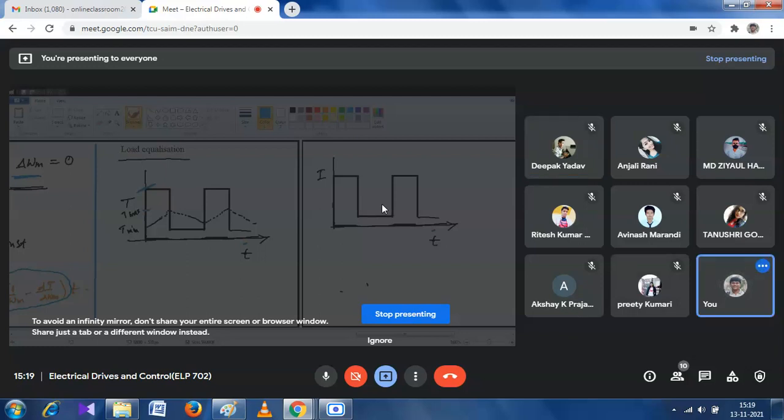एक्चुअल जो सिस्टम है वो फ्लक्चुएटिंग नेचर है. The nature of the current of actual system is fluctuating, so it may disturb the voltage level of that system. To reduce the fluctuation in voltage level or say stability of that system, we have used such a thing that we can suppress the fluctuation. What we make an arrangement by which we actually suppress the fluctuation, that arrangement is called load equalization.